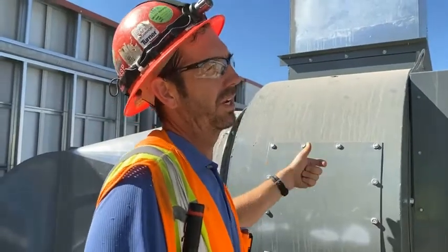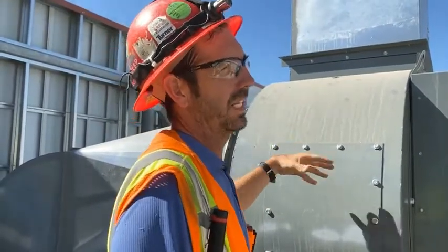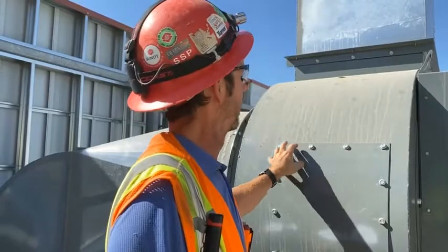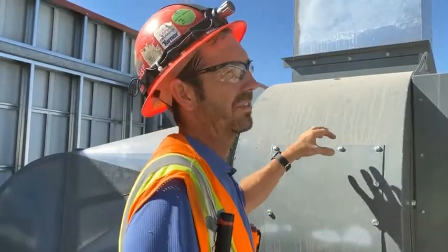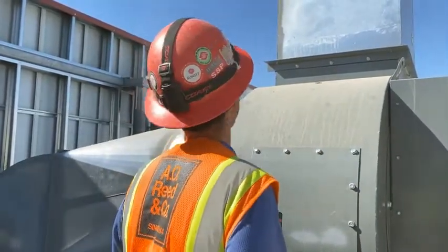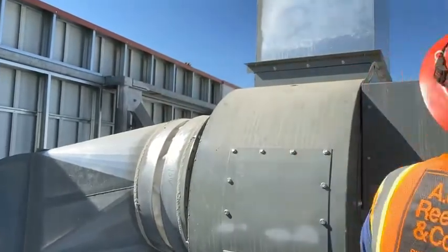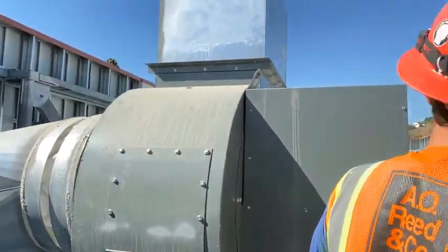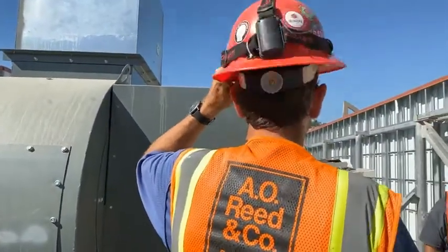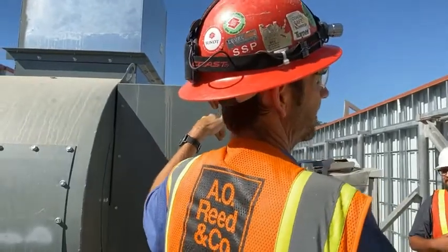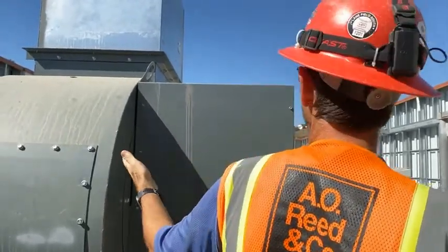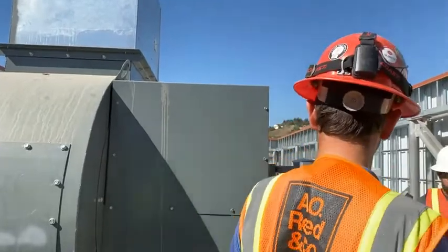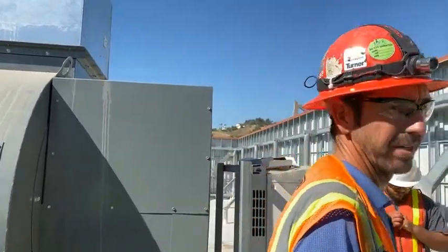Like annually, you'll want to check the tightness of the wheel. When you're cleaning it, make sure all the set screws are still tight. This is the inspection door into the wheel itself, the set screws on that. Any questions on these 2 fans? Centrifugal utility fan. Feeds the production kitchen.